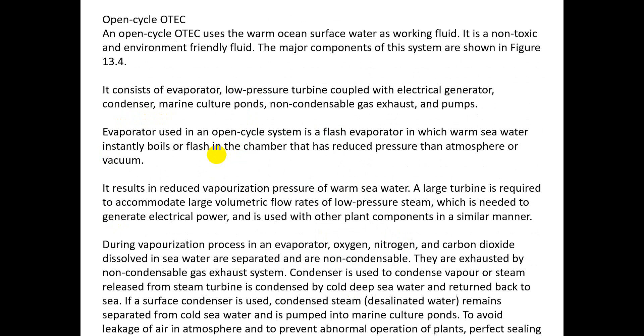The evaporator used here is an open type system — a flash evaporator in which warm sea water instantly boils or flashes in a chamber at reduced pressure below atmospheric, creating a vacuum. This results in vaporization of the warm sea water. A large turbine is required to accommodate the larger volumetric flow rate of the low pressure steam needed to generate electrical power.